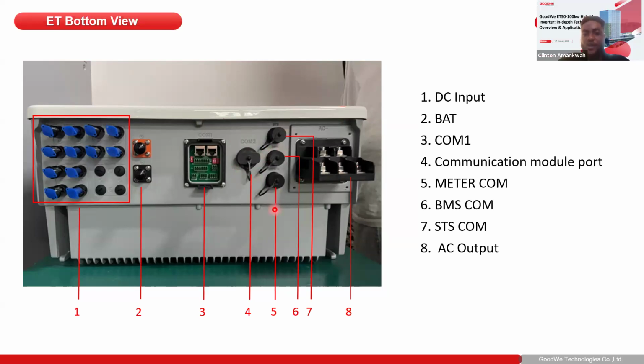Starting from number 5, we have the meter COM port. This serves as a communication port to establish communication between your external smart meter, the GoodWe smart meter GM330, and your inverter. With this, you are able to do export control as well as read your incoming grid power. Now we also have the BMS port, labeled number 6, which serves as the communication port for your lithium-ion batteries. With this, you can establish communication between your lithium-ion battery on site and the inverter, achieving discharge and charge control.